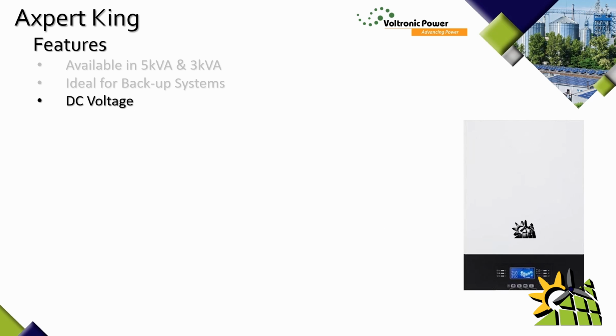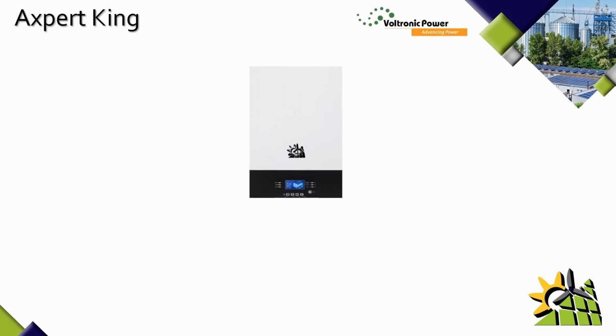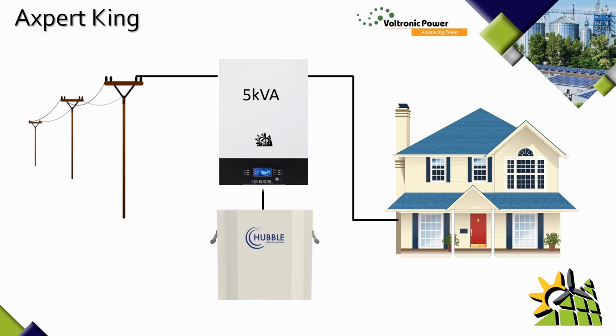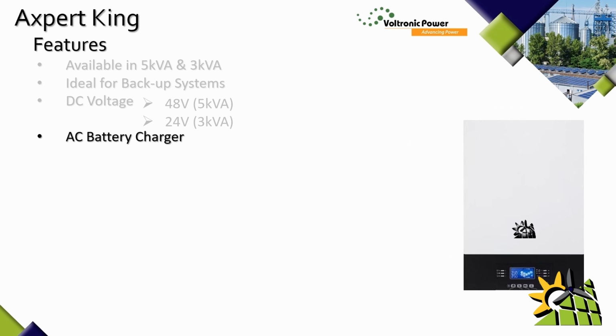Now, the DC voltage, which is the battery voltage, is available at 48 volt on the 5 kVA inverters and 24 volt on the 3 kVA inverters. So on a 5 kVA inverter, you should only connect a 48 volt lithium battery, also known as a 52 volt lithium battery. And on a 3 kVA inverter, you could only connect a 24 volt battery, also known as a 26 volt battery. The size of the AC battery charger that is built into the inverter is 60 amps on the 5 kVA inverter and 60 amps on the 3 kVA inverter.